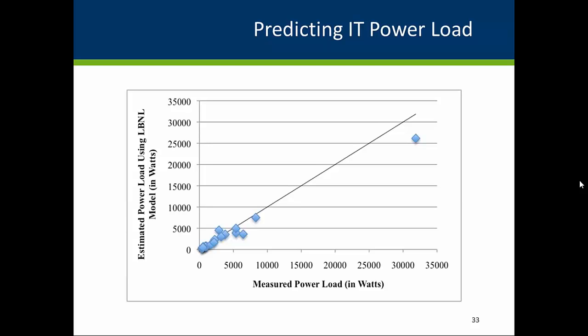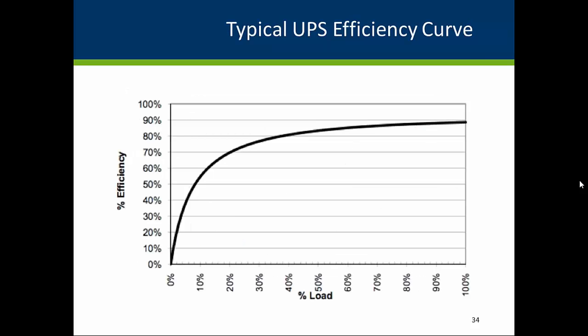In addition, we also used typical power draws for other IT equipment in the server racks, as well as for typical PoE devices like phones and access points that drew power from the network switches. This approach allows us to estimate SEDC power load by counting servers, hard drives, network ports, and PoE devices. The graph shows a comparison of the estimated values versus the actual measured power loads of each SEDC in the study. The diagonal line represents exact agreement. The good agreement shown in this graph suggests that this approach could be used to calculate deemed savings for IT measures. Let's now look at some specific measures.